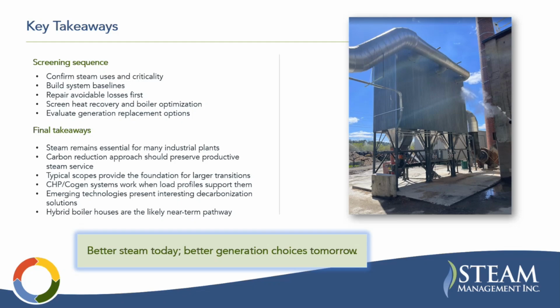That's a great question. All traps are good. I would say people don't typically monitor smaller traps like radiator traps on low pressure steam systems. Monitoring all traps is a good idea, but typically it's just a cost versus reward thing. So the things that are considered are the things that drive savings from steam trap losses, which are going to prioritize higher pressure traps, higher run hour traps, and larger traps. Also, though, critical process traps. So if the facility has, say, a heat exchanger that's on a critical process and you really want to make sure that trap is functioning properly, that would be justification for monitoring.